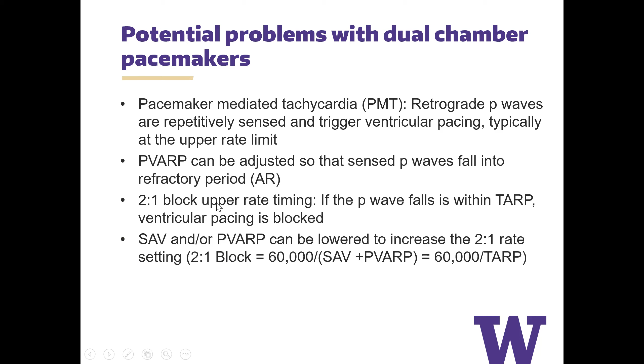So if the P wave falls within another refractory period, this is a total atrial refractory period, ventricular pacing is blocked. And so if your atrial rate is suddenly very fast and exceeds the rate that's set by the total atrial refractory period, then you will see behavior such as 2-to-1 block or even higher levels of block. I'm going to skip this math here.